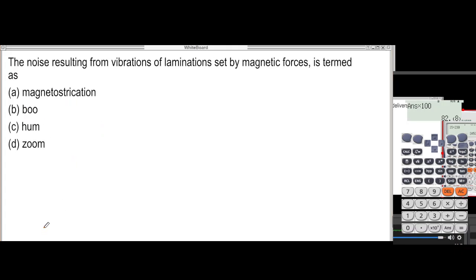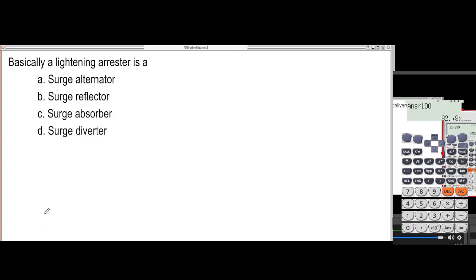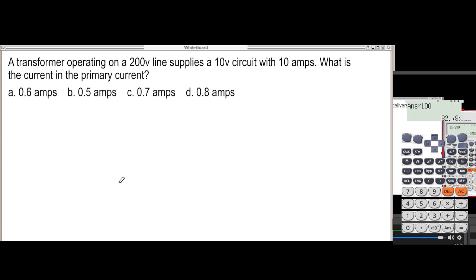The noise resulting from vibration set by magnetic forces is termed as the hum. This is applicable to a transformer, that kind of sound. So that is hum. Basically, a lightning arrestor is also a surge diverter. It diverts the surge so that instead of going to our line, it goes to the ground, thereby protecting our transformer. A transformer operating on a 200 volt line supplies a 10 volt circuit with 10 amperes.